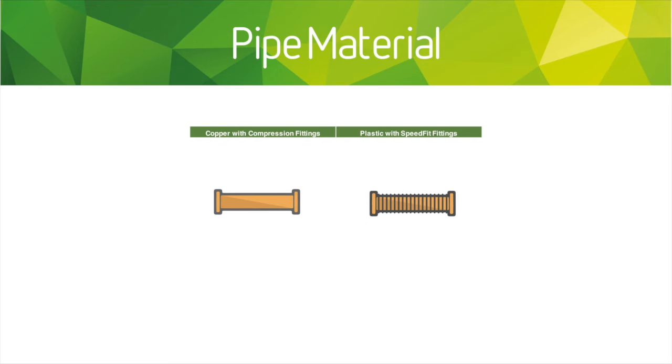The advantage with copper is I would actually recommend a compression fitting type. So you use a tool to compress the pipe together, so it's just copper on copper with no hot works on site. The system is still quite quick to install, but because it's slightly less forgiving, you have to think through the routes and where pipes are going to go, so it actually gets installed a little bit better than plastic, because more often plastic is just bunged in without being supported correctly. But if it is done correctly, as I said at the beginning, then both systems are suitable for heating systems.